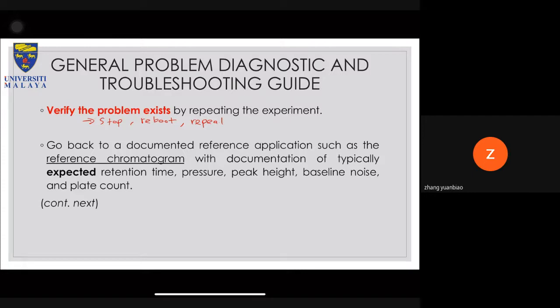So by doing this, sometimes what might happen is that there might be some signal miscommunication between your HPLC system and your computer. And once that happens, it will just go beep, beep, beep, beep, beep, and then it stops the whole run and tells you there's an error in this area or that area. So if the error actually comes out for the second time, right after you did all these 3 things, stop, reboot, and repeat, then you know, okay, something has actually gone wrong, and you need to therefore investigate.